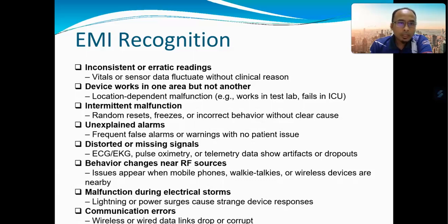And then we also can recognize EMI when the medical device malfunctions during an electrical storm, right? Basically, sometimes lightning or power surge can cause strange device responses, right? And then the last one, EMI also can be recognized through communication errors, right? So maybe you can see wireless or wired data links drop or collapse.